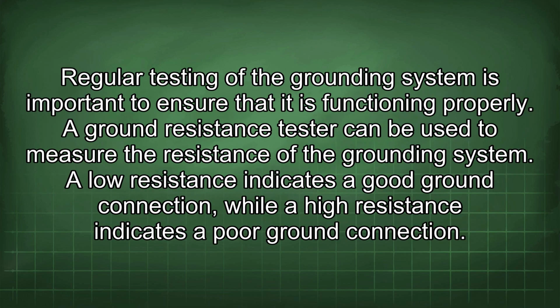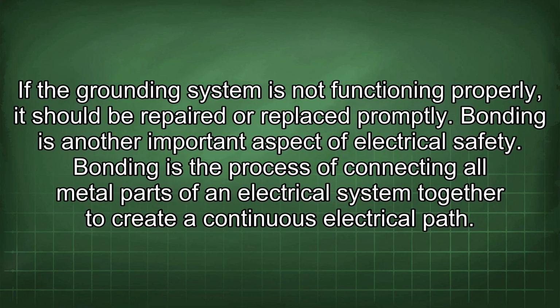Regular testing of the grounding system is important to ensure that it is functioning properly. A ground resistance tester can be used to measure the resistance of the grounding system. A low resistance indicates a good ground connection, while a high resistance indicates a poor ground connection. If the grounding system is not functioning properly, it should be repaired or replaced promptly.